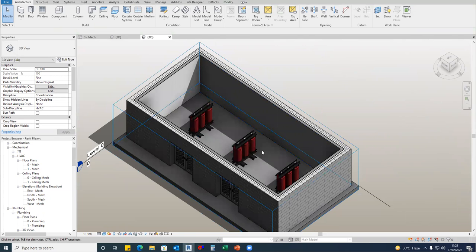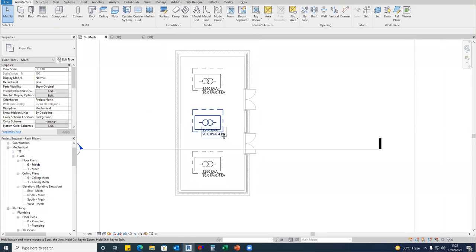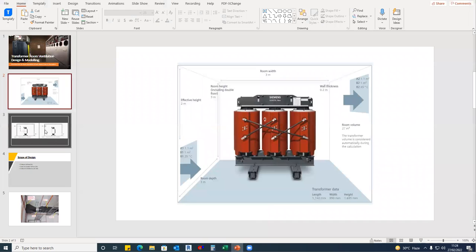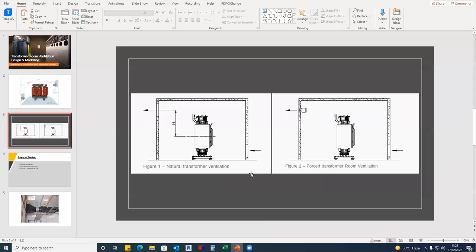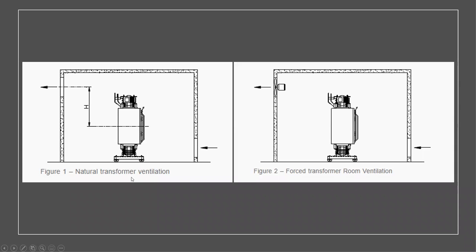So इस room का ventilation, if we have to do the ventilation of this area, okay, I'll go to the plan and open that. So it can be either natural ventilation, we can do the natural ventilation or forced ventilation. Okay, so for forced ventilation we require a fan. Okay, we require a fan for the exhaust and fresh air. In natural ventilation no fan is required, and this can be naturally taken from outside. So either we can provide a louver door, or if it is not a louver door, we can provide fresh air louvers. Okay, and natural ventilation does not require any fan for exhaust.